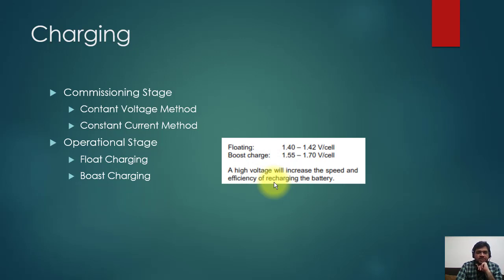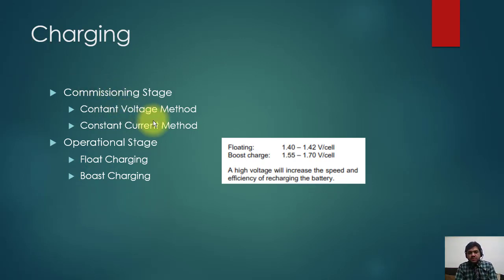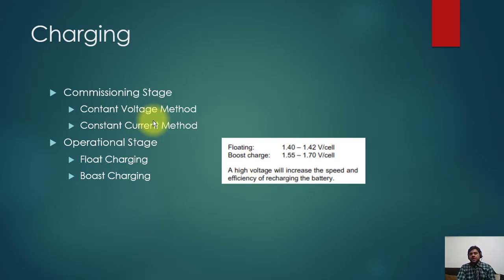There are two stages: commissioning and operational. During the commissioning stage, you must charge the batteries for the first time — this takes considerable effort if they have never been charged before. You can use the constant voltage method, where voltage is kept constant and current varies, or the constant current method, where current remains constant and voltage varies. In the operational stage, there are two charging methods: float and boost. Normally the battery remains on float charge. The float charge voltage per cell is approximately 1.4 volts. The boost charge voltage is higher, around 1.55 to 1.7 volts. If the battery voltage drops below a set level, the charger automatically switches from float to boost, then returns to float once charged.